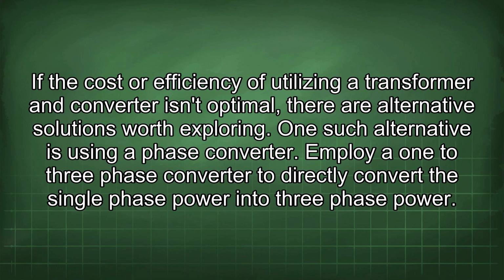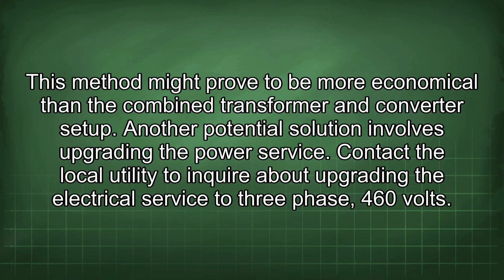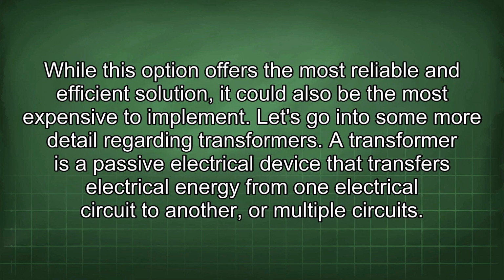If the cost or efficiency of utilizing a transformer and converter isn't optimal, there are alternative solutions worth exploring. One such alternative is using a phase converter. Employ a 1 to 3 phase converter to directly convert the single-phase power into three-phase power. This method might prove to be more economical than the combined transformer and converter setup. Another potential solution involves upgrading the power service. Contact the local utility to inquire about upgrading the electrical service to three-phase 460 volts. While this option offers the most reliable and efficient solution, it could also be the most expensive to implement.